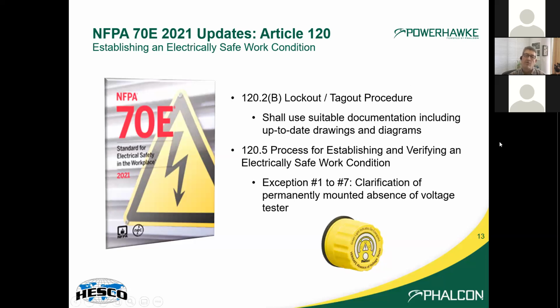Right after the 2018 version, Panduit came out with this device, and there was a bit of a kerfuffle in the standard world as to how this would work. The reason we call Panduit out is this is a device we install that HESCO can provide. It's a great device to help eliminate the hazard of a qualified person having to go in and expose themselves to testing for verification of absence of voltage. Got a quick little video here.